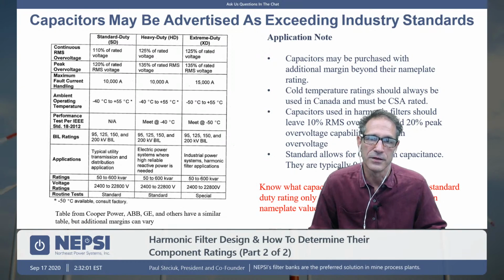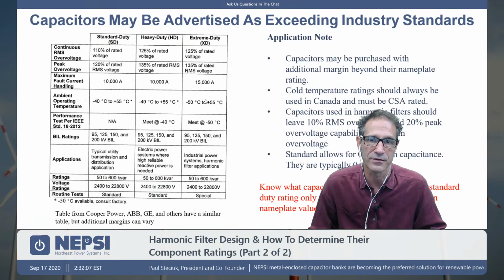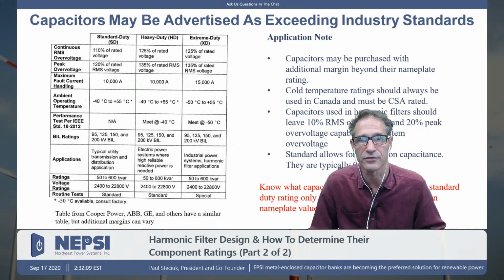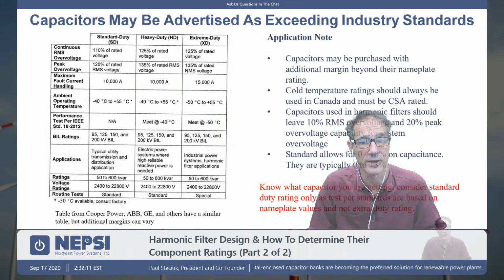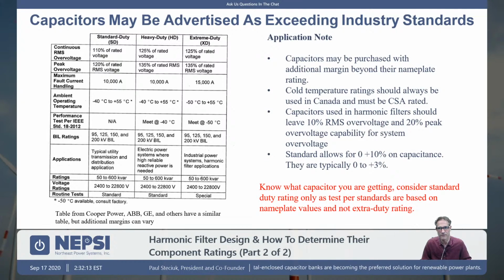One of the key differences between standard duty and extreme duty is the temperature rating. The extreme duty can go down to -50 C. This is a factor up in Canada. When we're supplying up into Canada, we're making sure that the capacitors are chosen based upon -50 C because it does get that cold up there.